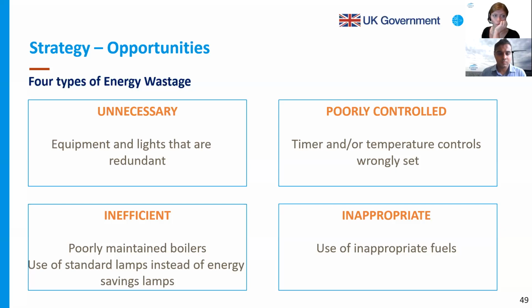The second category is poorly controlled. So any systems, timers, temperature controls that are wrongly set, there is a good opportunity to reduce wastage in this area. Another type of wastage is just the result of inefficiencies. So this could include poorly maintained boilers, the use of standard lamps instead of energy saving ones. And then the last category of energy waste is just simply inappropriate processes. So in this case, the use of inappropriate fuels could result in a great deal of wastage. Next slide.